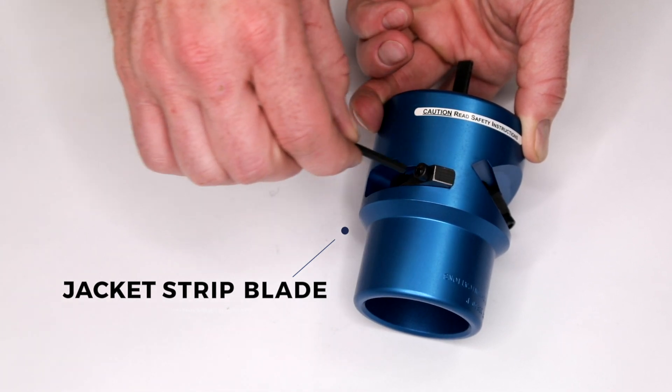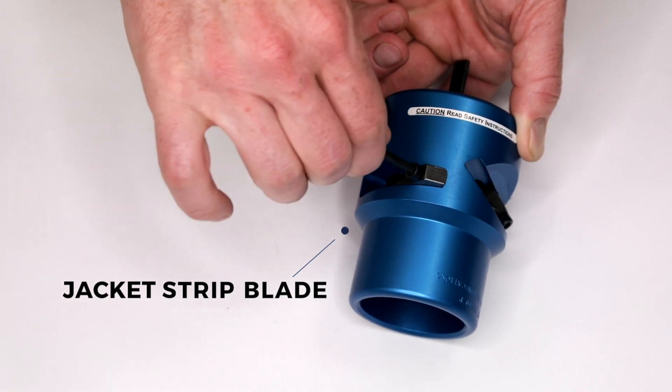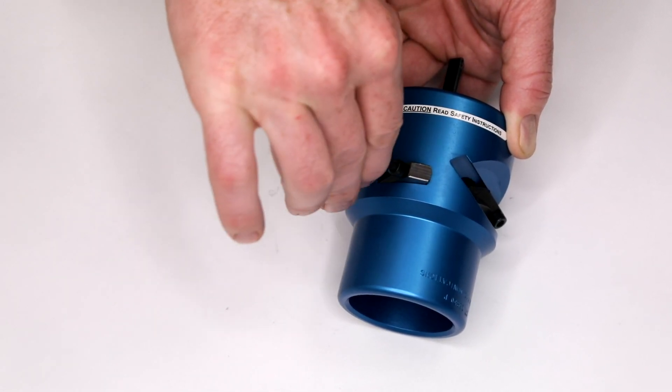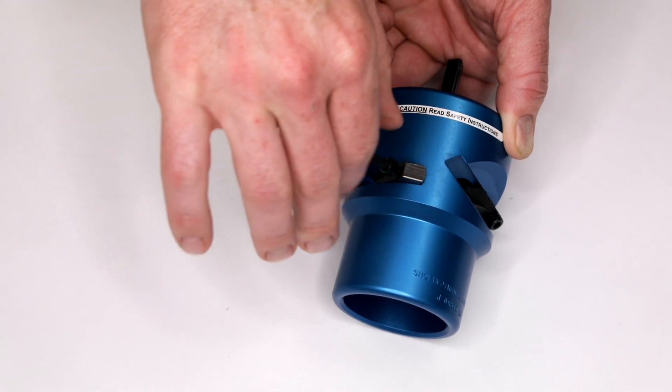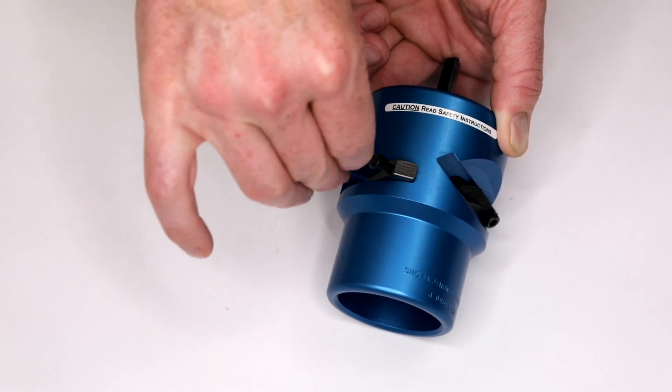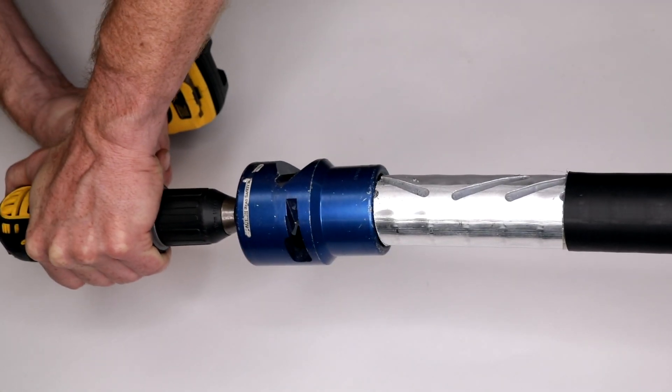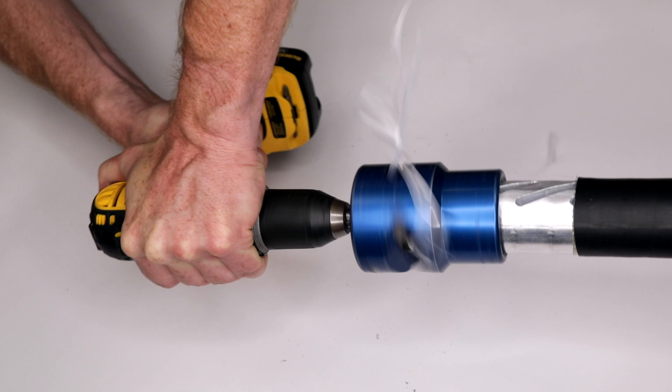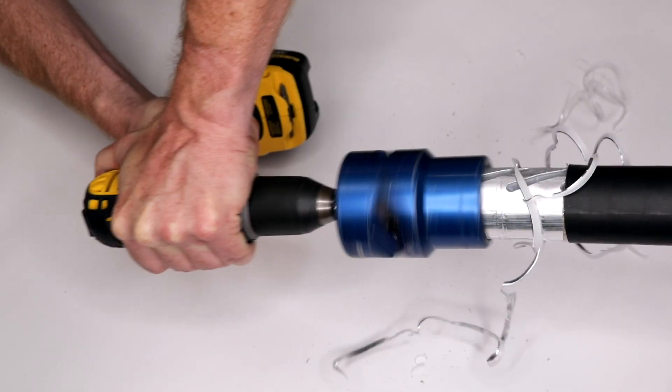Next, slide the drill-mounted cable prep tool onto the cable end and operate in a clockwise direction. Continue until the tool no longer cuts away material and remove the prep tool while still in motion.